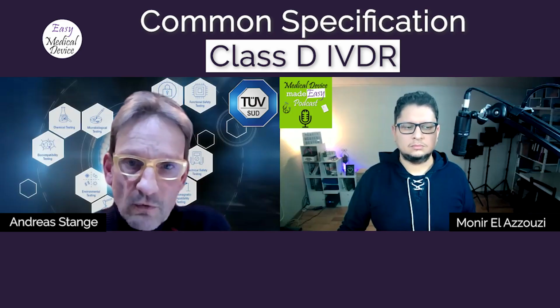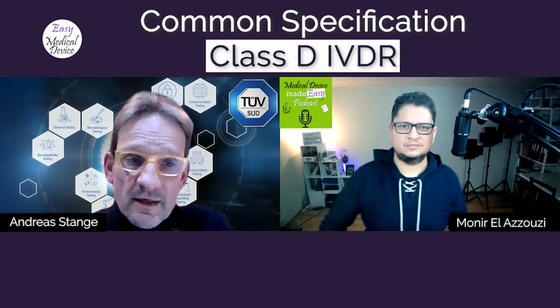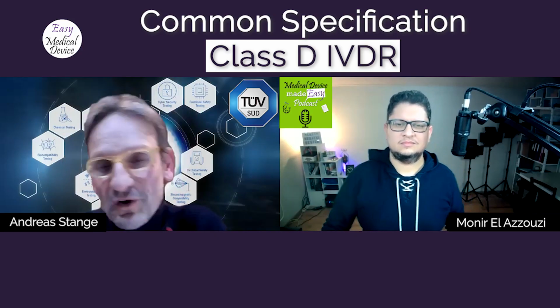And now under the IVDR, the regulation very clearly says that manufacturers shall comply with these common specifications. So there is basically no excuse not to do that. If they don't want to, they must have very good reasons and explain that in great detail, and it will be very difficult.